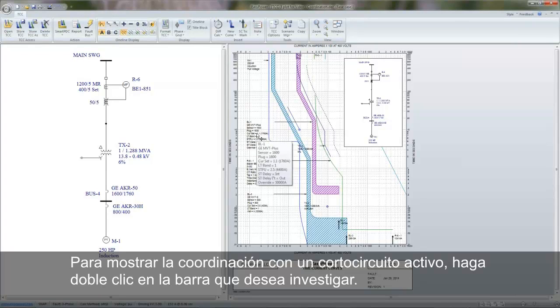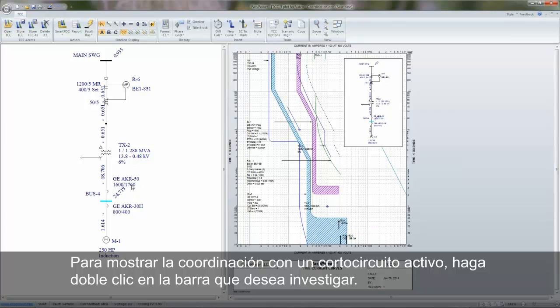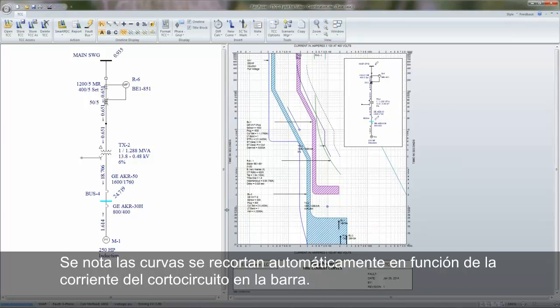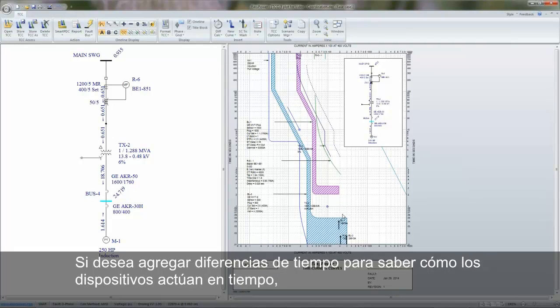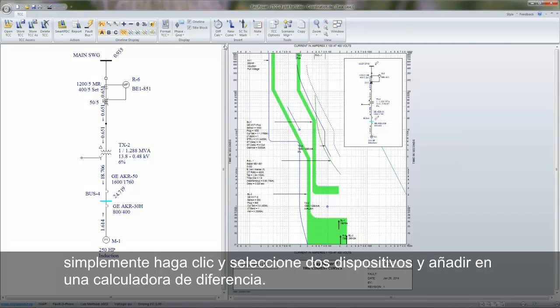To show coordination with an active short circuit, double-click on the bus that you want to fault. Notice that the curves are automatically clipped according to the short circuit at the bus. If you want to add time differences to know how devices are timing, simply click and select two devices and add in a difference calculator.